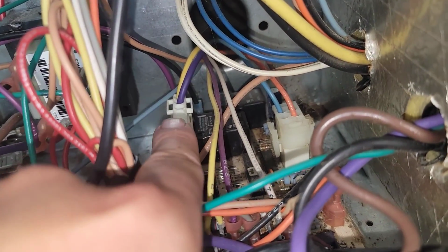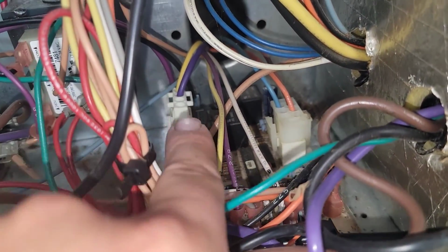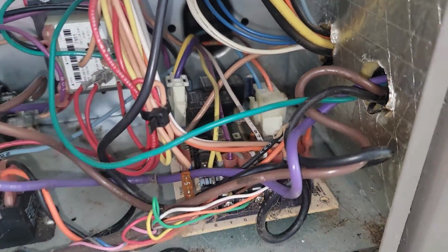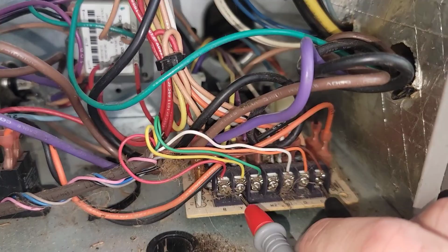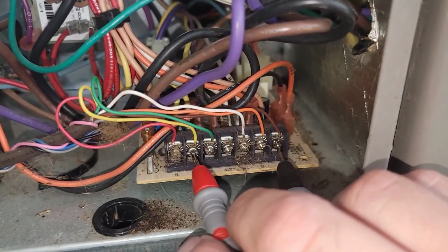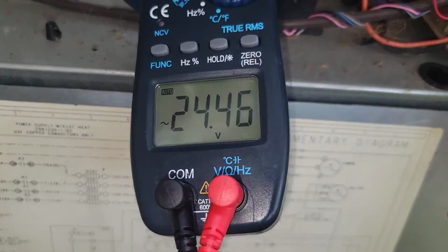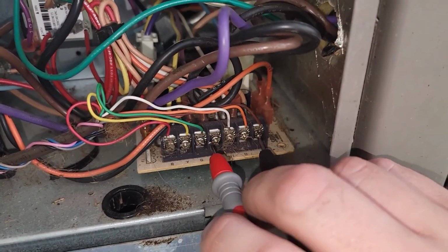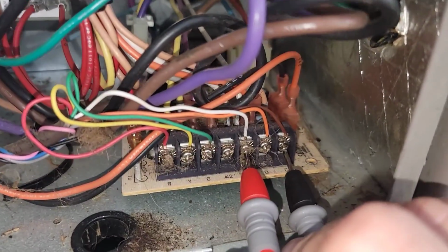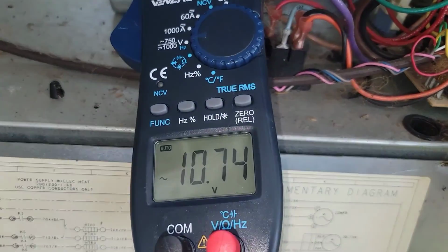See, there's a plug right here. You see that plug with the yellow and purple wire? That is used to send power to one of the heat strips. The unit kicked on, so I'm checking from C to yellow, right, to see if I got a call. Got a call for cooling. Now I'm going to check to the W. Okay, call for the heating.